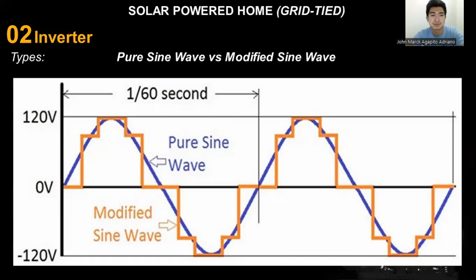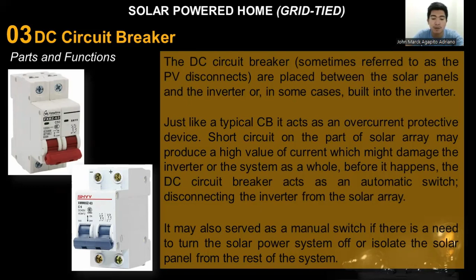DC circuit breaker, parts and function. The DC circuit breaker, sometimes referred to as the PV disconnects, are placed between the solar panels and the inverter, or in some cases built into the inverter. DC circuit breakers act as automatic switch, disconnecting the inverter from the solar array. It may also serve as a manual switch if there is a need to turn the solar system off or isolate the power panel from the rest of the system.